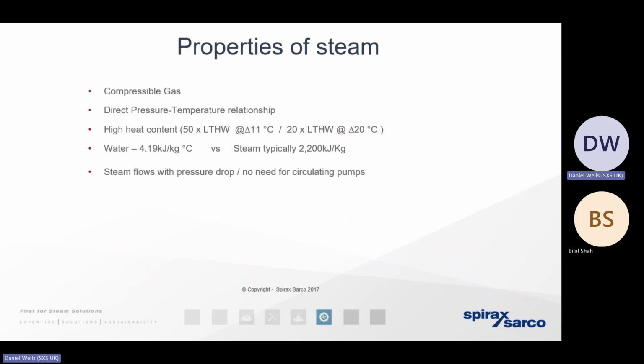We've already mentioned we don't need pumps with the steam system. The steam's a gas, it moves in accordance with the pressure drop around the infrastructure. Water-based systems, whether they're produced by a gas-fired boiler or by heat pumps, will need a much, much larger infrastructure because it's got a reduced energy content, it's got a greater volume, but we're also going to require those circulating pumps as well. Not so with steam.